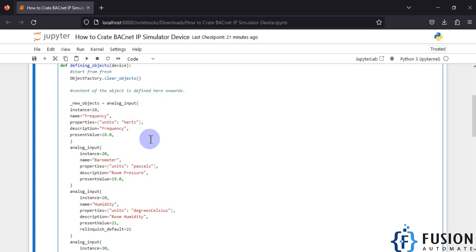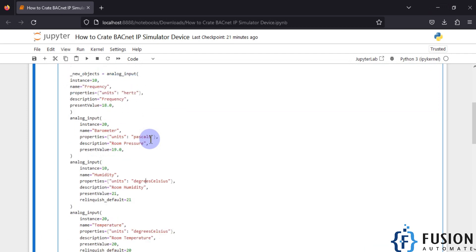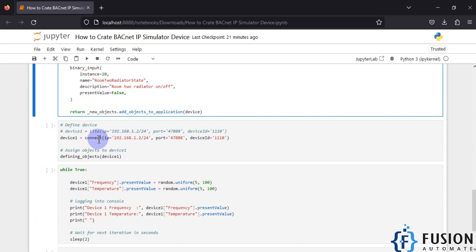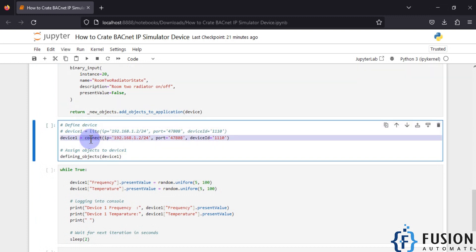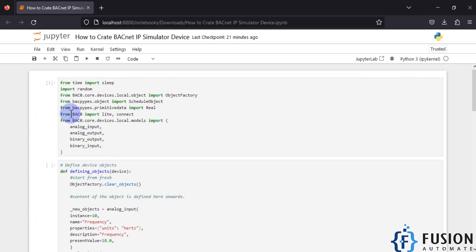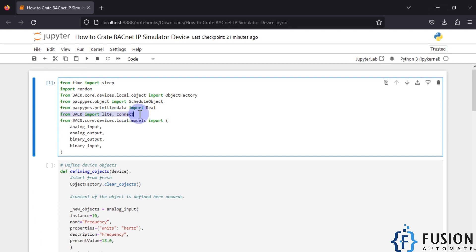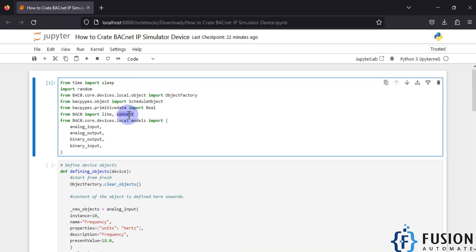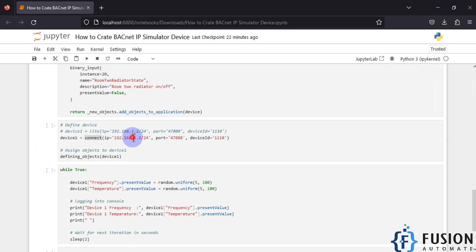We need to assign those objects to our device, but first we need to create our device. Scrolling down, you can see 'define device' — device one is set equal to connect. The connect function comes from back zero: from bac0 import lite and connect. If you are using a Raspberry Pi you can use lite, and if you are using a Windows system or heavy machinery you can use connect for better performance.